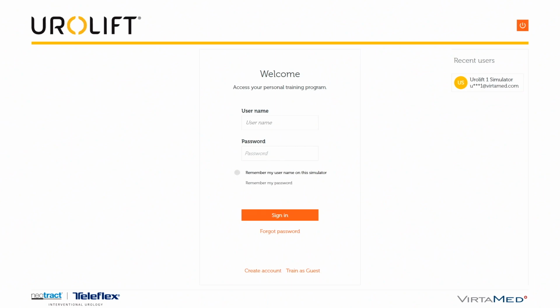Each simulator has been assigned a number, and for quick use, it is preloaded with a user. You will find this on the top right under Recent Users. In our example, this machine has the user UroLift 1 Simulator. For most applications, you will select this option. Doing so will auto-populate the username and password. These details can also be found on a sticker on the back of the monitor.